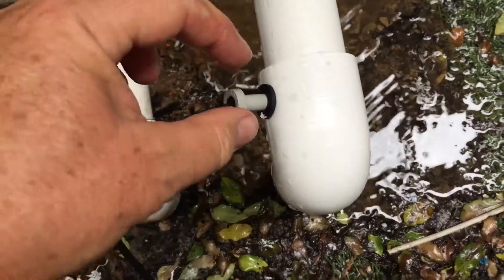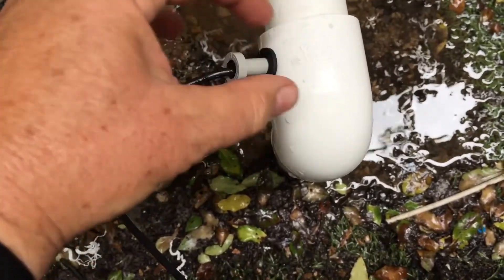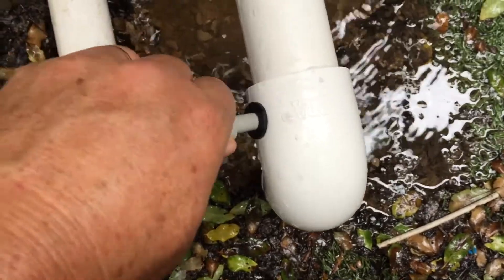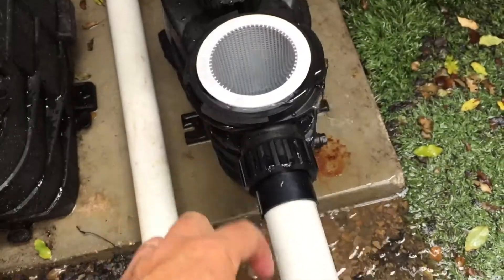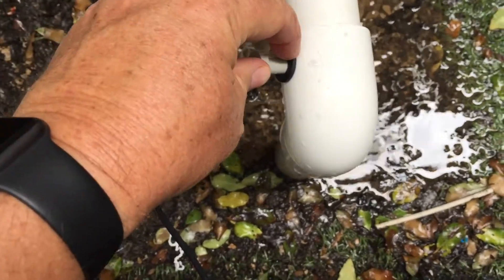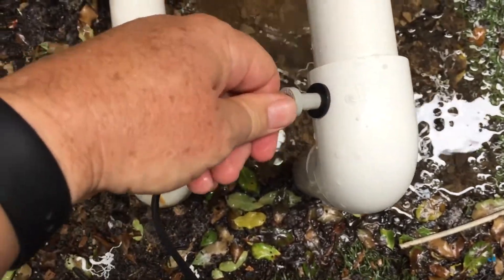If you do get a bit of an air leak, don't panic — just pull it off again, put a bit of silicone on the rubber grommet, put it in, and then a bit of silicone on the probe and put it in, and that'll seal it up. It is important on the suction side that you don't get an air leak, so when you test it, you need to listen to make sure there's no air getting in.